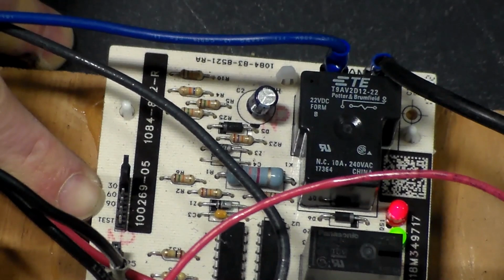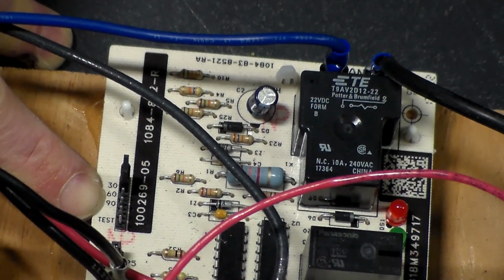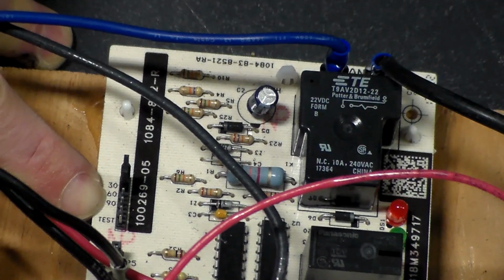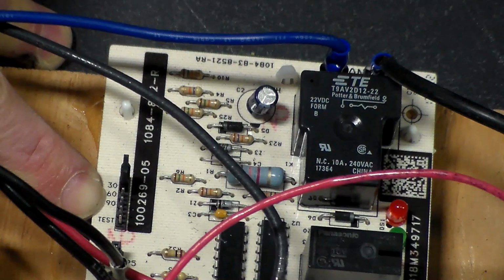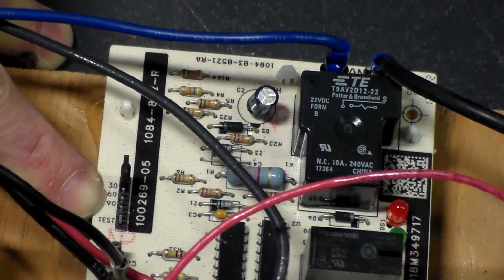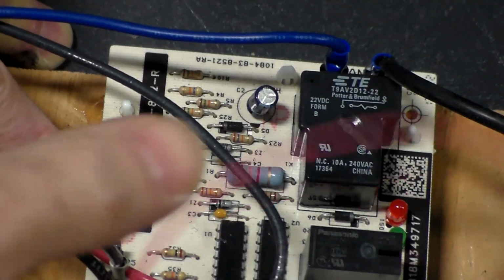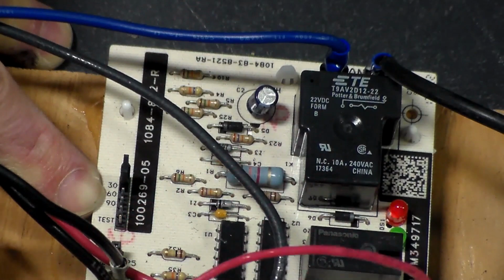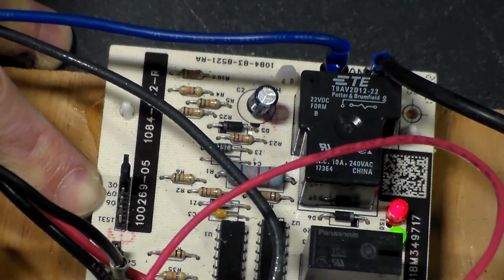The test right there is how we test defrost. When this thing's calling for heat, when you have a normal defrost sensor, you're going to need to jump out the defrost sensor like I have here. I put these two red wires here jumping out my defrost sensor, but you can do it with just some jumper wires.